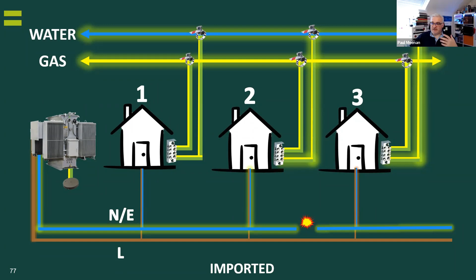That's the imported version. Exported is this: single dwelling, transformer, could be on a pole, combined neutral and earth, break on that neutral, it's going to use whatever parallel low impedance path it can. Okay, and then somebody maybe a few miles away may pick it up. So that's diverted neutrals. It's really important because of this.